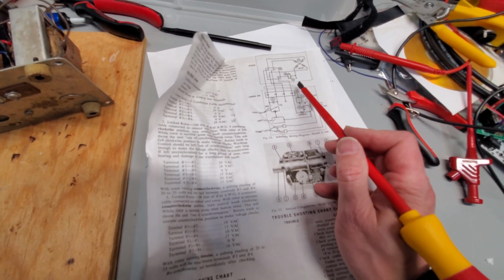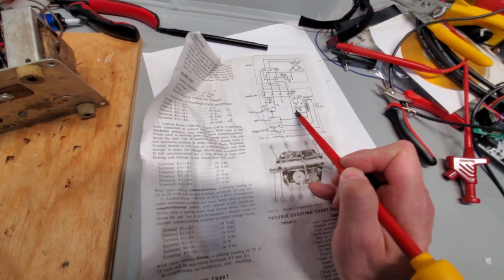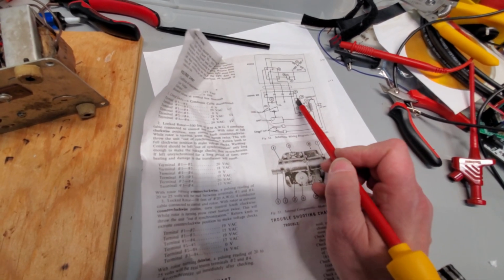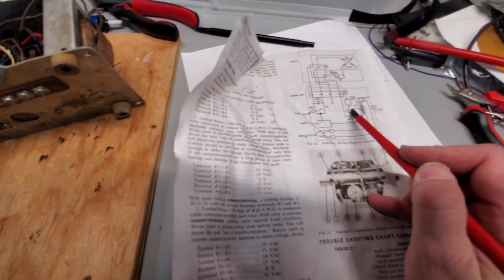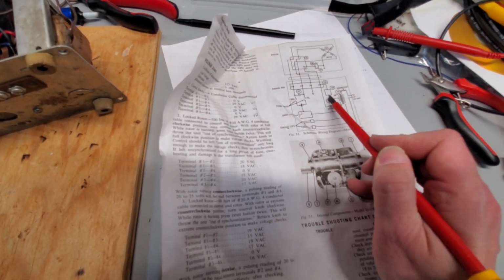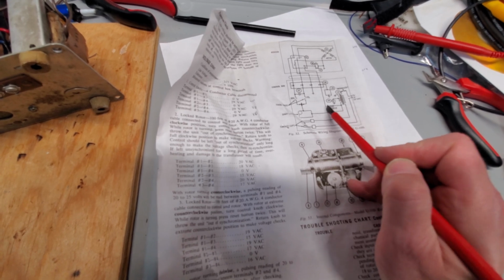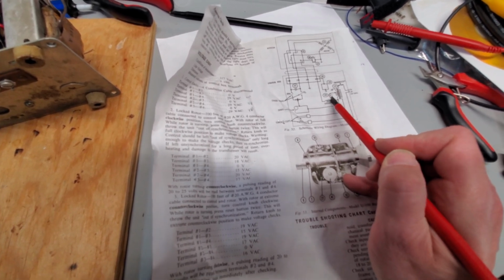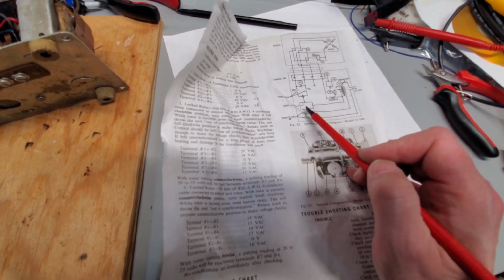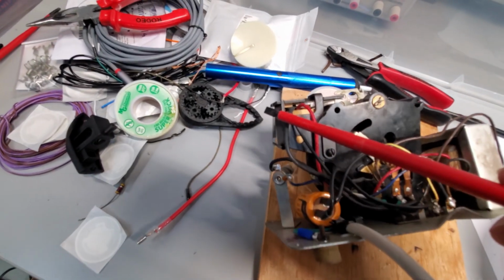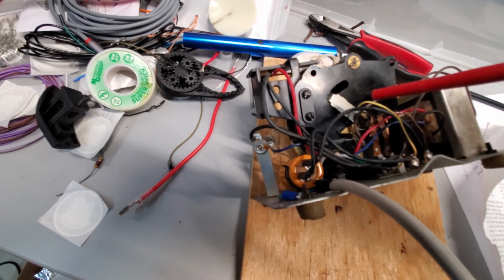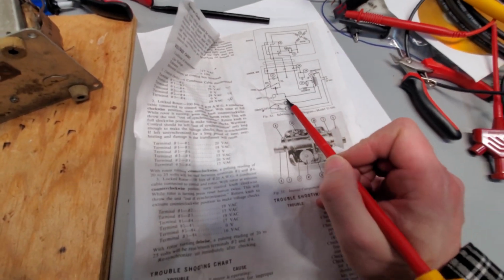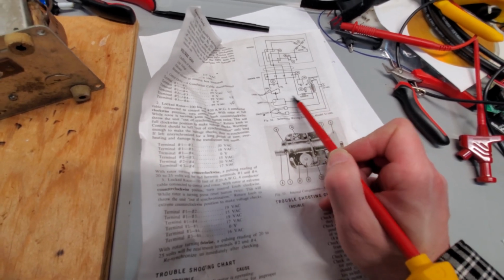So what that does is close the solenoid here to ground, just like that manual switch which we see down here - that manual switch also grounds the solenoid. So that activates the solenoid, and the solenoid makes the whole mechanism move on. Right here is the solenoid that gets pulled down, and this whole mechanism rotates one more step - that's the clicking noise you hear when it's running.